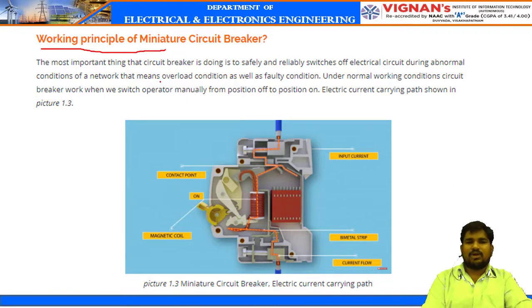Under normal working condition, the circuit breaker works when we manually switch the operator from position on to off. This MCB can be used for overload protection and fault protection, as well as for manual operating. For example, if you want to do any maintenance in our existing electrical network, what we need to do? We just switch off the supply of one room. So during maintenance, we need to have a provision to switch on or off the network. That's why the MCB is also used as a switching mechanism from position off to position on or vice versa.